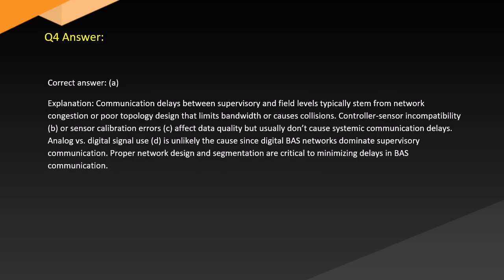Answer. Correct answer: A. Explanation. Communication delays between supervisory and field levels typically stem from network congestion or poor topology design that limits bandwidth or causes collisions. Controller sensor incompatibility, B, or sensor calibration errors, C, affect data quality but usually don't cause systemic communication delays.